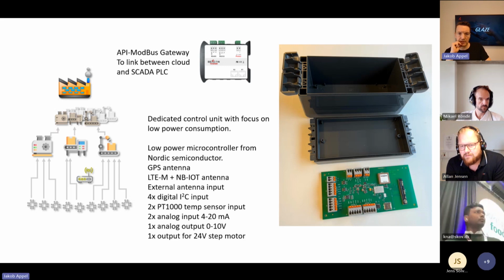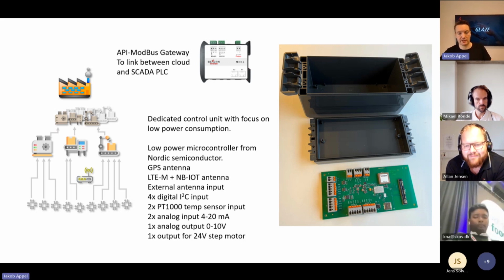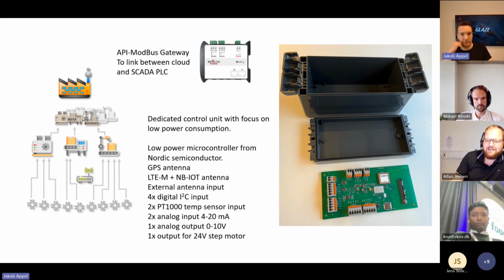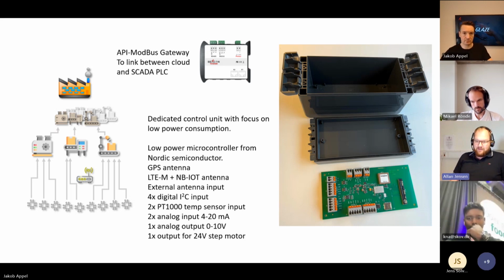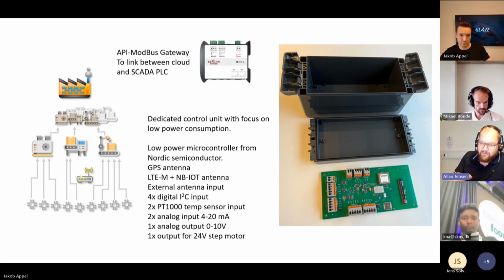Can I ask you a short question? Is it not so that you put a set point to your control box, and then it will control the valve automatically, so that it's done locally once you have sent that? You're totally right. Yes, we are sending a set point for the bypass, so it could be 60 degrees in the summer times, where we would like to have a bypass, and then the built-in microcontroller has PID regulation to adjust the motor valve to secure the 60 degrees. And the other way, in the winter times, we just need a frost protection, and then we will have 2 degrees instead of 5 degrees.